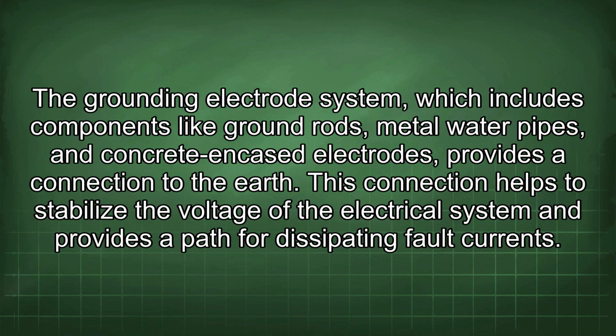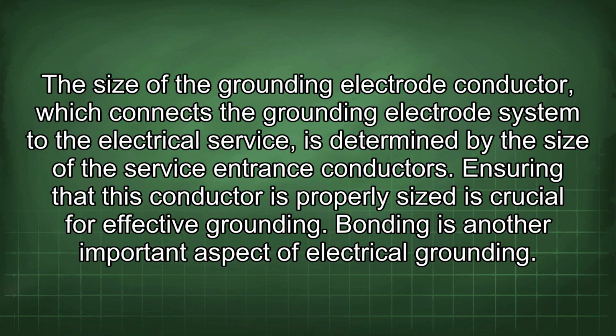The grounding electrode system, which includes components like ground rods, metal water pipes, and concrete encased electrodes, provides a connection to the earth. This connection helps to stabilize the voltage of the electrical system and provides a path for dissipating fault currents. The size of the grounding electrode conductor, which connects the grounding electrode system to the electrical service, is determined by the size of the service entrance conductors. Ensuring that this conductor is properly sized is crucial for effective grounding.